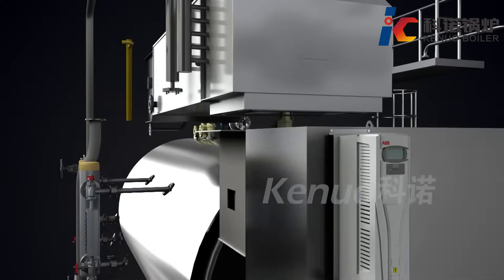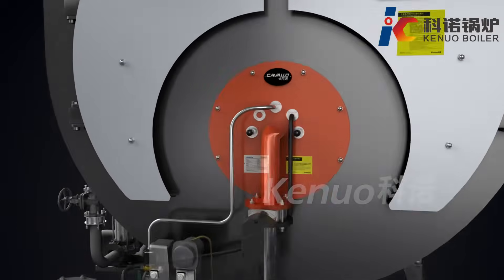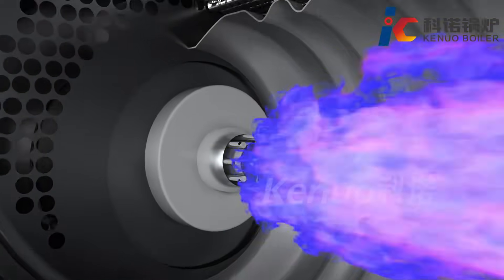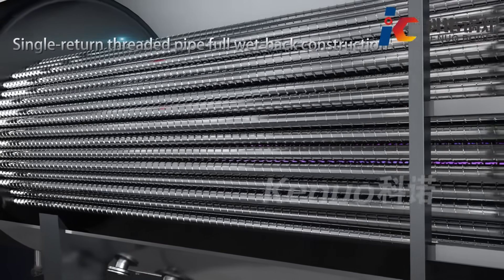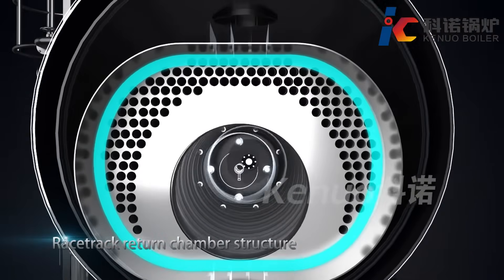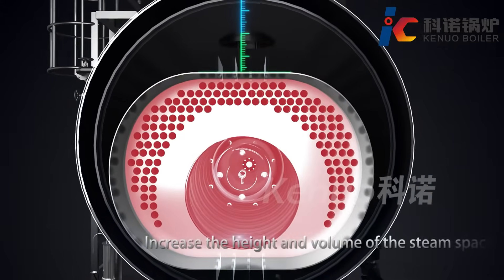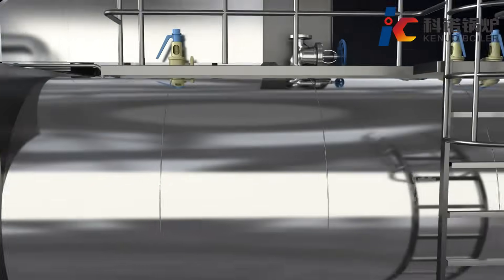The furnace is arranged symmetrically in the lower center of the boiler, featuring a corrugated furnace, threaded smoke tube, and wet-back design. A raceway-shaped reverse chamber in the rear increases the height and volume of the steam space, making steam dryness up to 99.83%, ensuring steam quality and enhanced load change response.